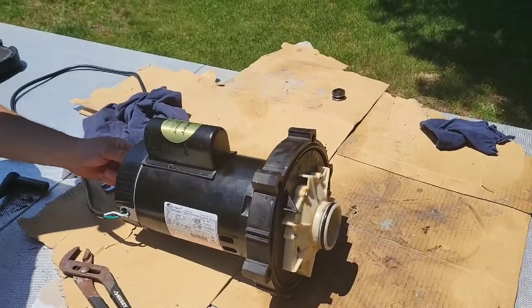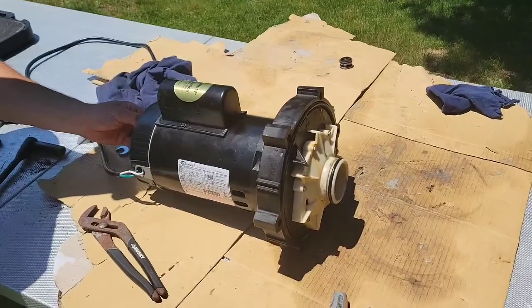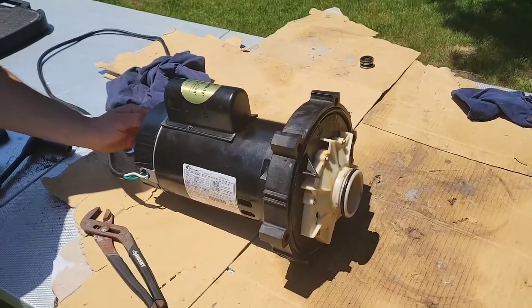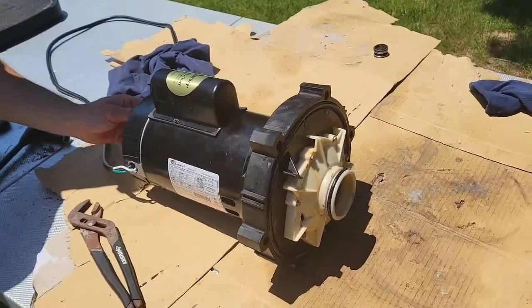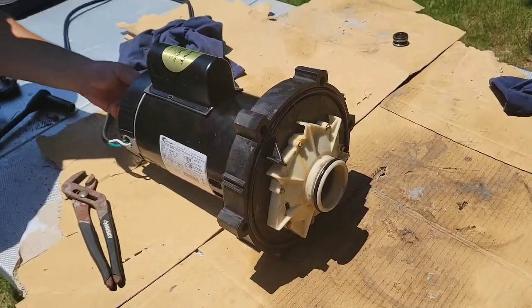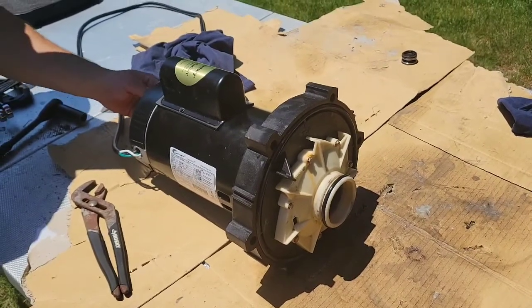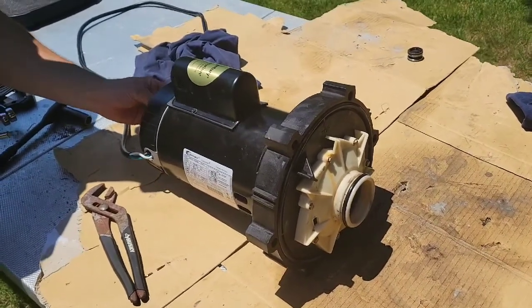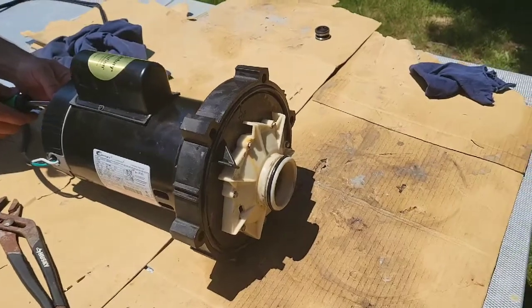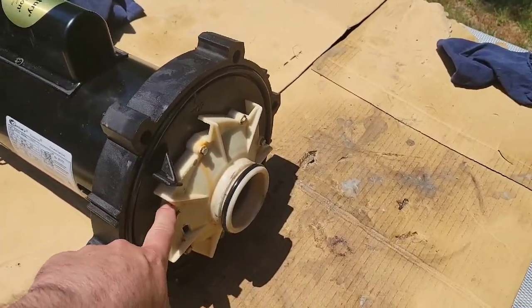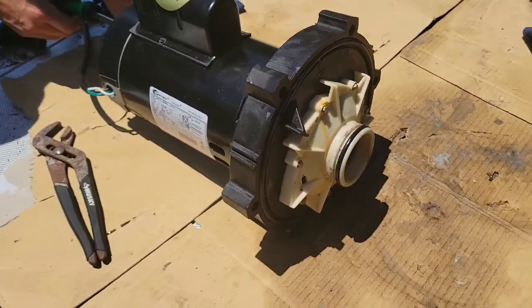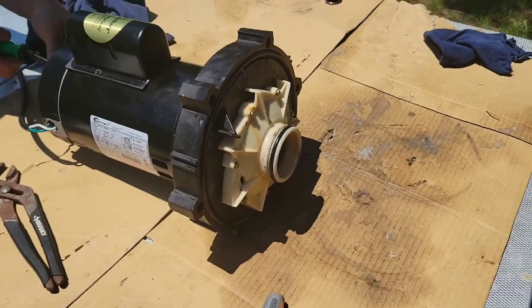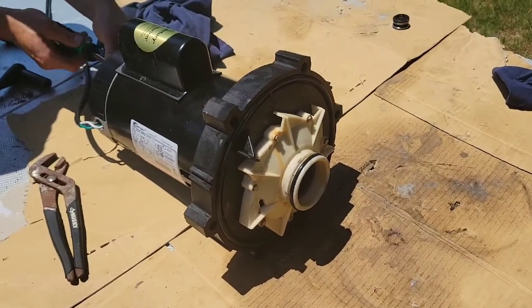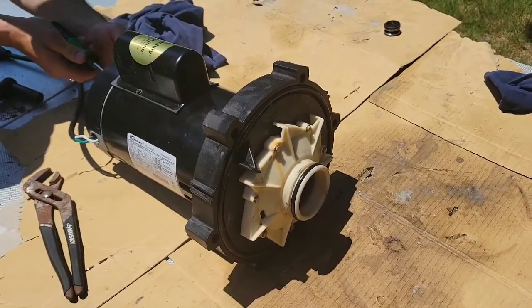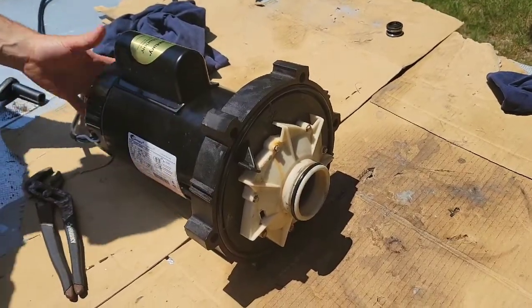Joe lost power to his pump, so he decided to change out the motor, and he did all that while it was leaking. We tried to tighten it and it was still leaking, so we decided to back it all off and inspect what he had done. It turned out that underneath the impeller, he had put the motor shaft seal on backwards, so the rubber grommet was rubbing against the ceramic pump motor end.